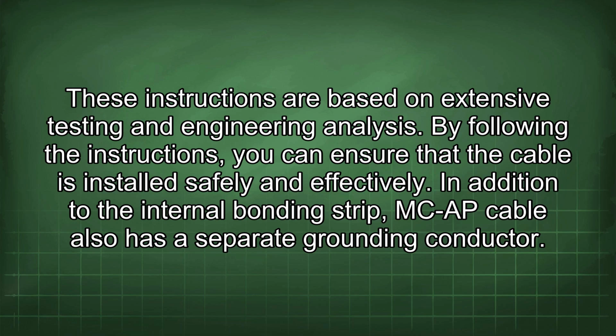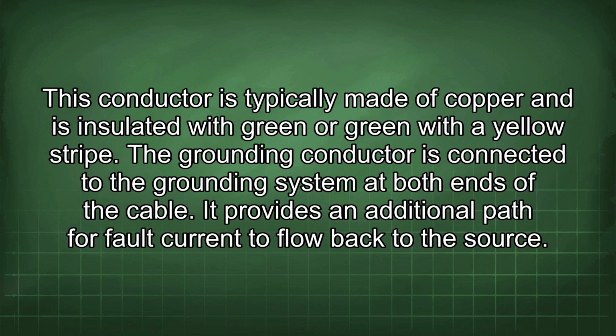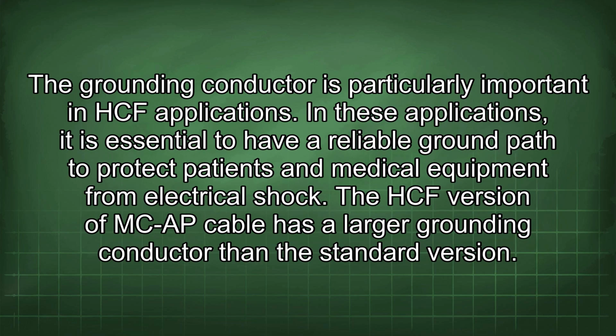In addition to the internal bonding strip, MCAP cable also has a separate grounding conductor. This conductor is typically made of copper and is insulated with green or green with a yellow stripe. The grounding conductor is connected to the grounding system at both ends of the cable. It provides an additional path for fault current to flow back to the source. The grounding conductor is particularly important in HCF applications. In these applications, it is essential to have a reliable ground path to protect patients and medical equipment from electrical shock.